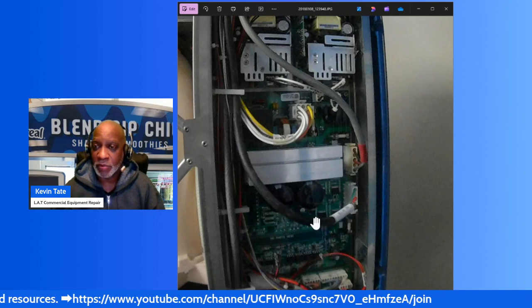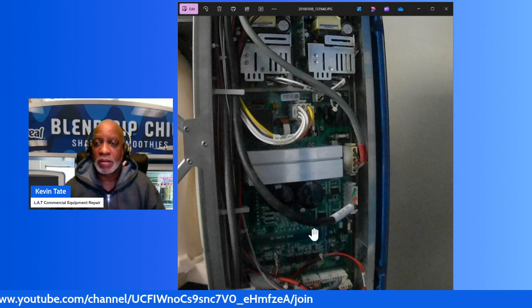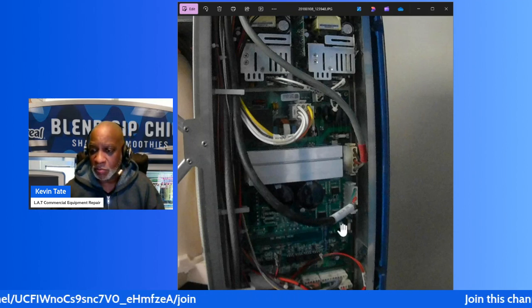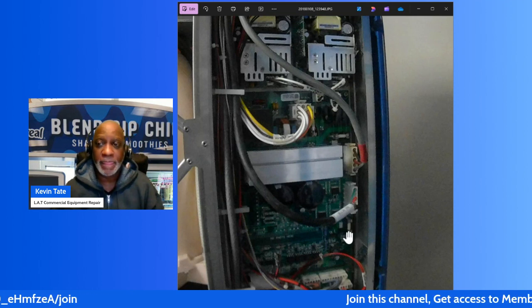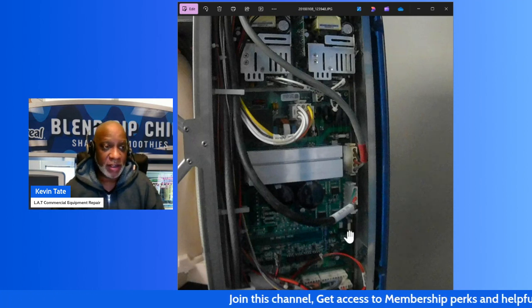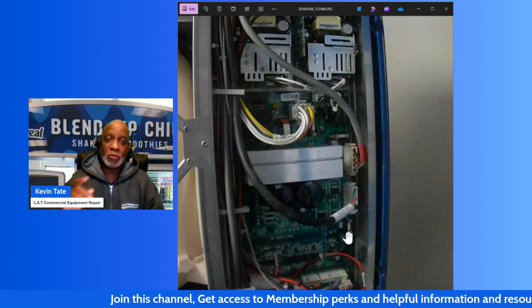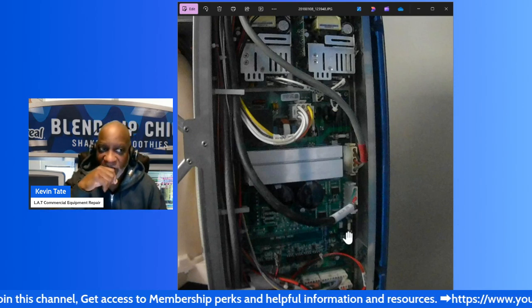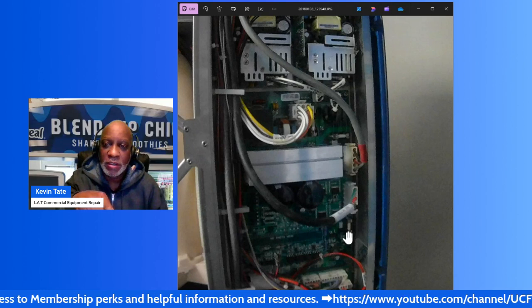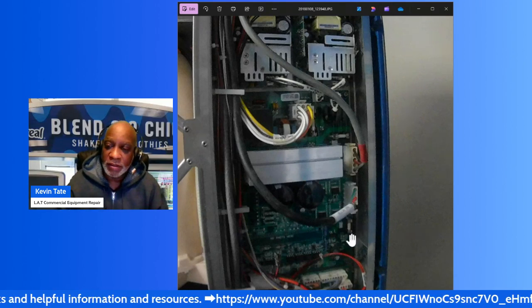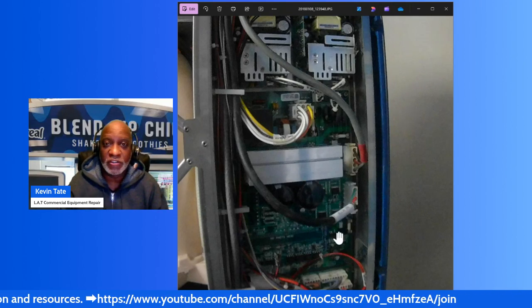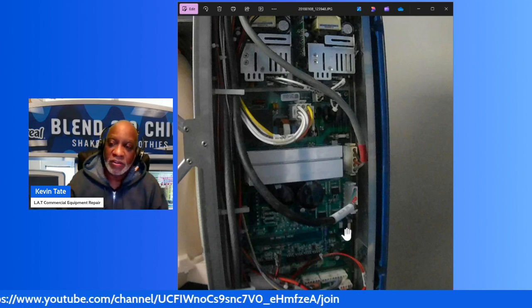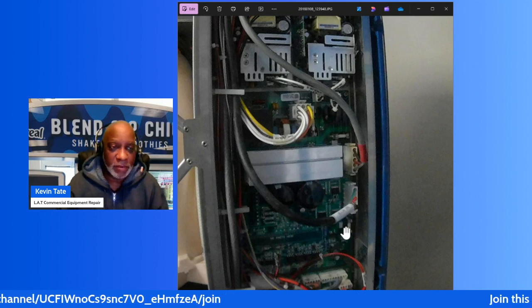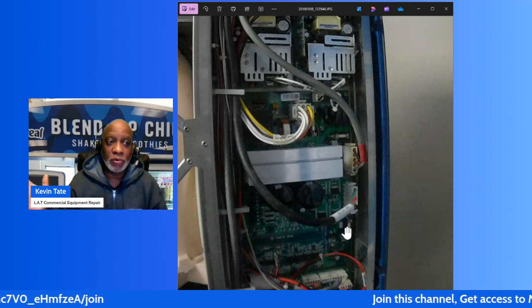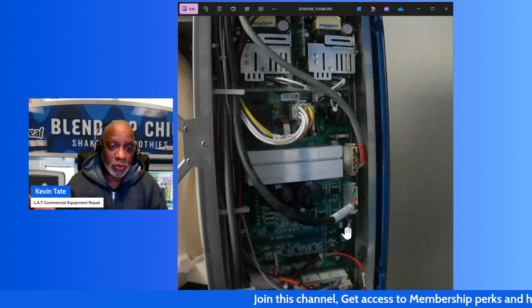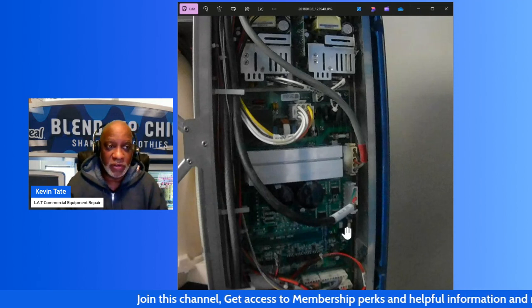So what happened was, when they tried it out, the mixer motor fuse had blown, and the electrician checked it and the fuse was blown. But what the electrician did was he went and took one of the fuses from the old board that he just took out - a good fuse from that - and put it in there, figuring it'll work fine now because now I have a new fuse in there and the fuse is good.